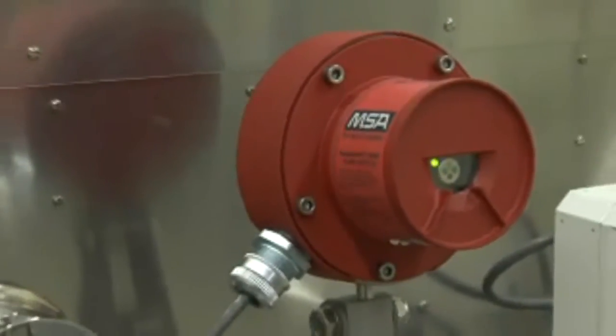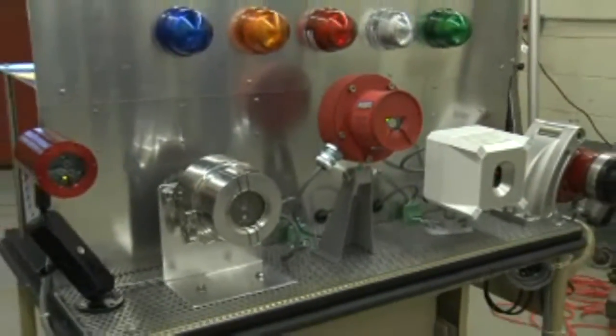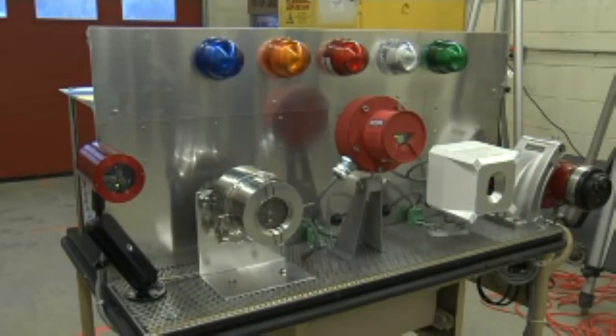Here is our portable test setup with all detectors mounted by the factory recommended brackets. From left to right we have Net Safety, Fire Sentry, MSA, Spectrex, and Det-Tronics. Each are tied to a light which activates as soon as the detector sees the fire.